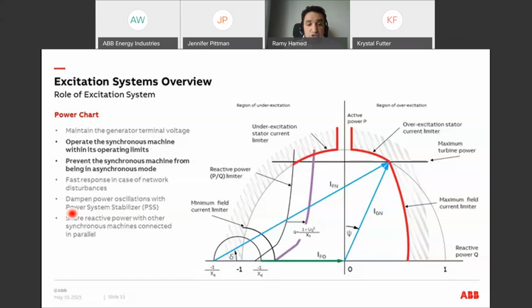The same goes for the generator. However, since the generator is such a critical equipment, we need to always monitor its operation and its limit. And so what we have here is the generator power chart, which we can consider as a graphical representation of the data sheet of the generator, which will tell us the limits of the generator and where we can operate safely.